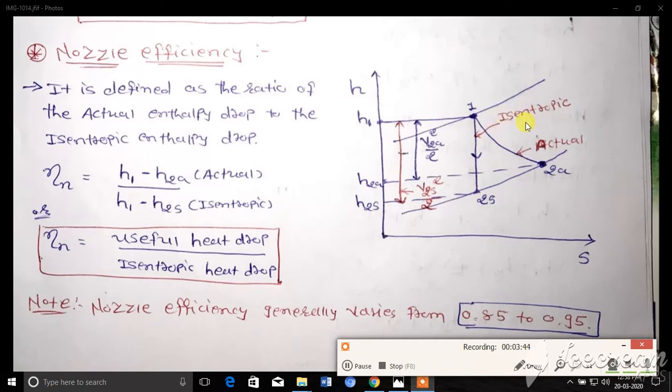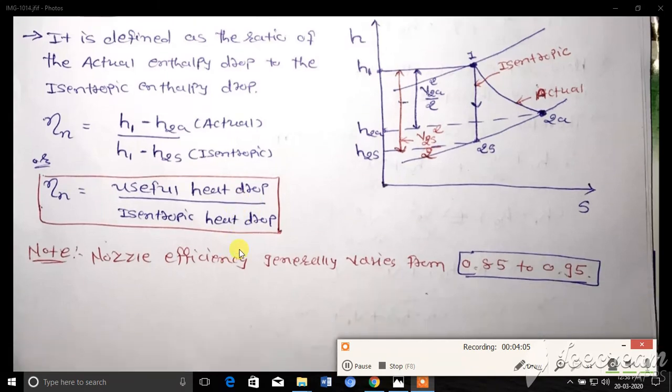Mathematically we can write nozzle efficiency as H1 minus H2A divided by H1 minus H2S. That is actual enthalpy drop divided by isentropic enthalpy drop. Eta n can also be written as useful heat drop divided by isentropic heat drop. Nozzle efficiency generally varies from 0.85 to 0.95.